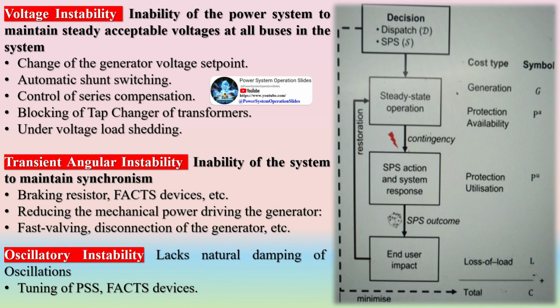Types of instability. System protection schemes are thus designed to initiate the final attempt at stabilizing the power system when a widespread collapse is imminent. As the risk for system collapse results mainly from the possible loss of stability, system protection schemes are generally designed to contain the different power system instability phenomena: frequency instability, voltage instability, transient instability, oscillatory instability.